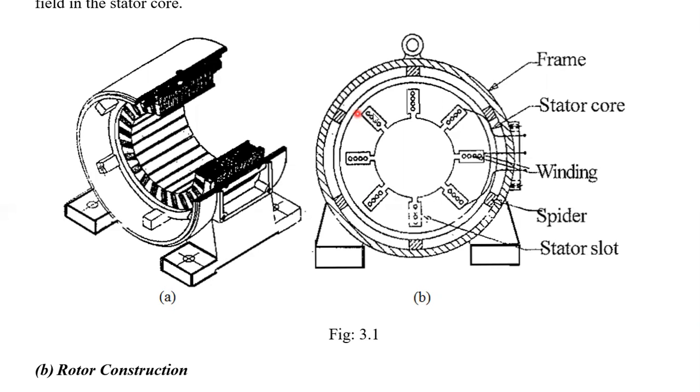RBY. So if you are changing the phase sequence, what happens? The rotating magnetic field rotates in the anti-clockwise direction. For RYB, I'm assuming clockwise direction. For RBY, the phase sequence is changed, and that's why the rotating magnetic field rotates in the anti-clockwise direction.